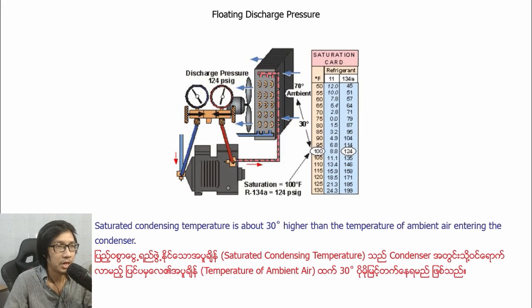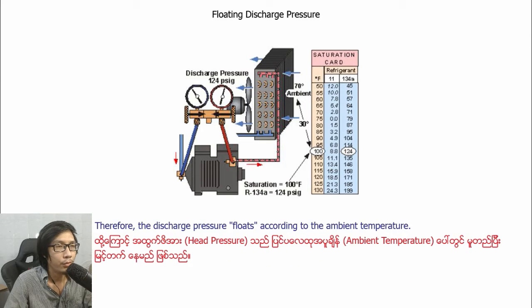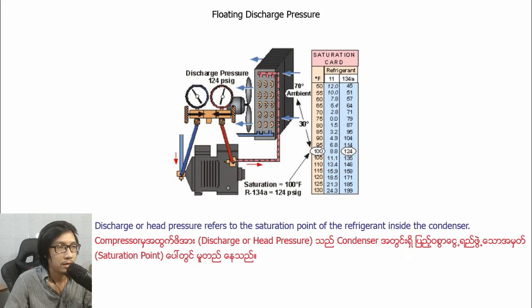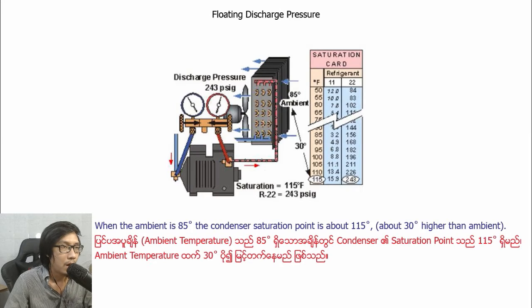Floating discharge pressure. Saturated condensing temperature is about 30 degrees higher than the temperature of ambient air entering the condenser. Therefore, the discharge pressure floats according to the ambient temperature. Discharge or head pressure refers to the saturation point of the refrigerant inside the condenser. When the ambient is 85 degrees, the condenser saturation point is about 115 degrees. About 30 degrees means about 30 degrees higher than ambient.